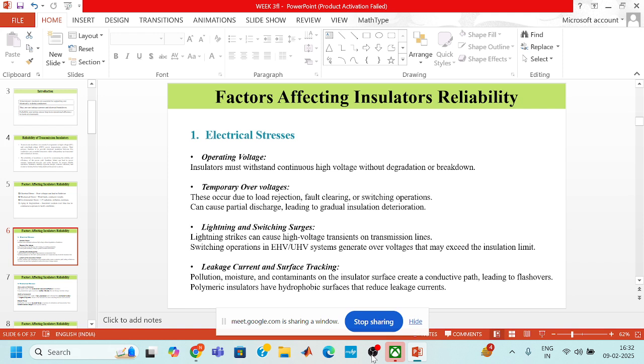Now third is lightning strikes. Lightning strikes can cause high voltage transients in the transmission system, and switching operations in EHV or UHV systems generate overvoltages that may exceed the insulation limits. Now fourth is leakage current and surface tracking. As we know, pollution, moisture, and contaminants on the surface of insulators can create a conductive path which leads to flashover, and polymer insulators have a hydrophobic surface that can reduce the leakage currents.